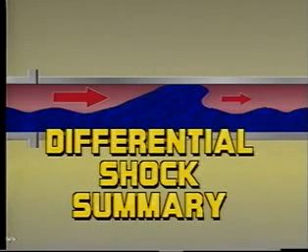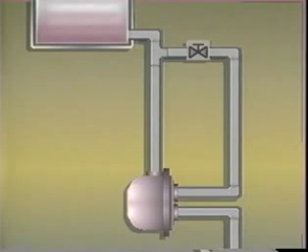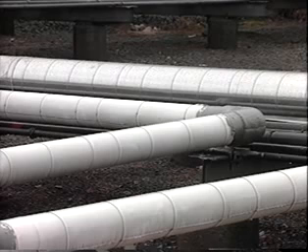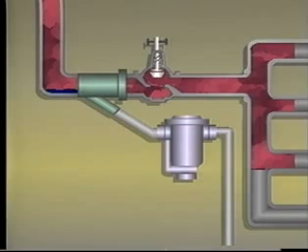To control differential shock, you must prevent condensate seals from forming in biphase systems. Condensate lines must be sized correctly and long vertical drops to the traps must be back vented. The length of the lines to traps should be minimized and the lines may have to be insulated to reduce condensing. The installation of a proper drip leg ahead of control valves will prevent differential shock from occurring when the control valve is opened after a period of closure.